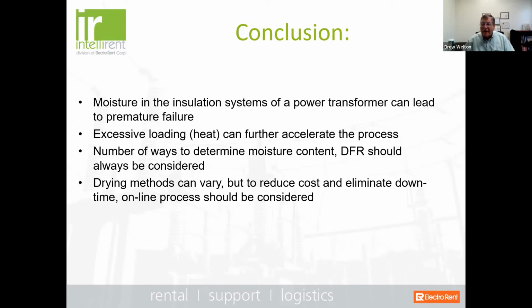I can say this, that if you look at an individual utility itself, a lot of it depends on the age of the transformer, the average age, and the way it's designed. The design has a big influence on the ingress of moisture, because if you have a free breathing conservator and your desiccant isn't very effective, you can have moisture ingress.